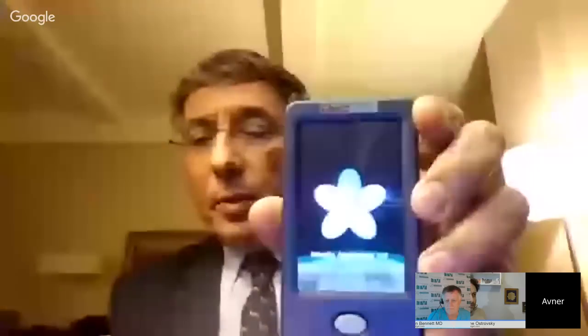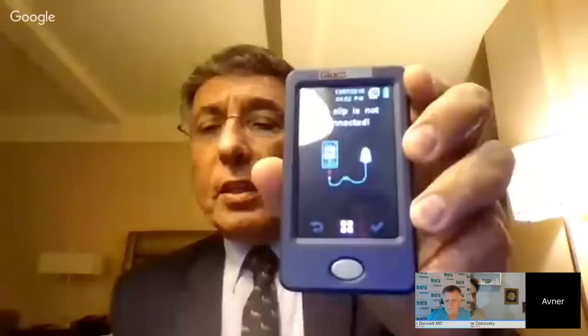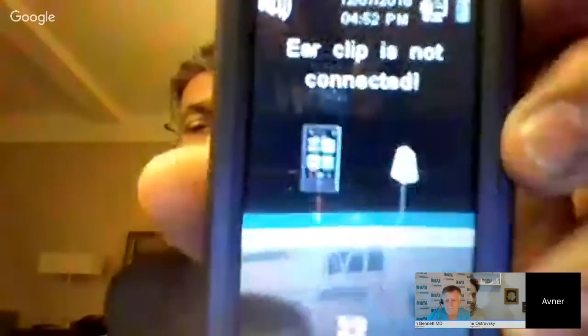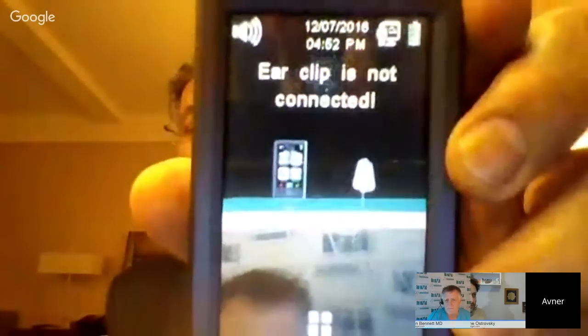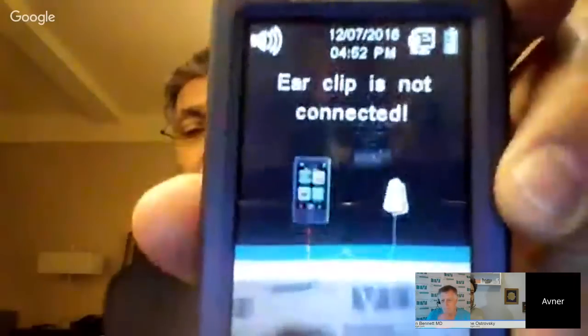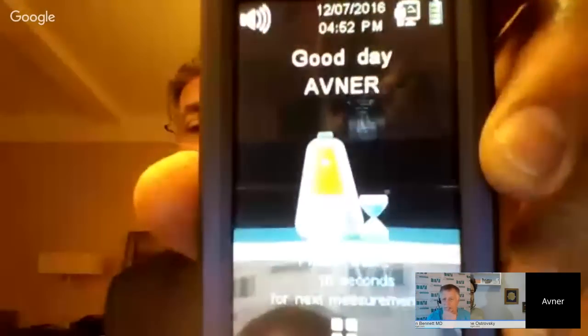So you saw the picture of the device. Now you can see it's not only a picture, it's a real device. To explain in short how it works, I turn it on. As you remember, I said that the device is user-friendly. So currently we can see that the device recognized that there is no ear clip attached. So therefore I attach the ear clip. And then immediately the device recognizes that that particular ear clip refers to me. Okay. It's calibrated for this one.